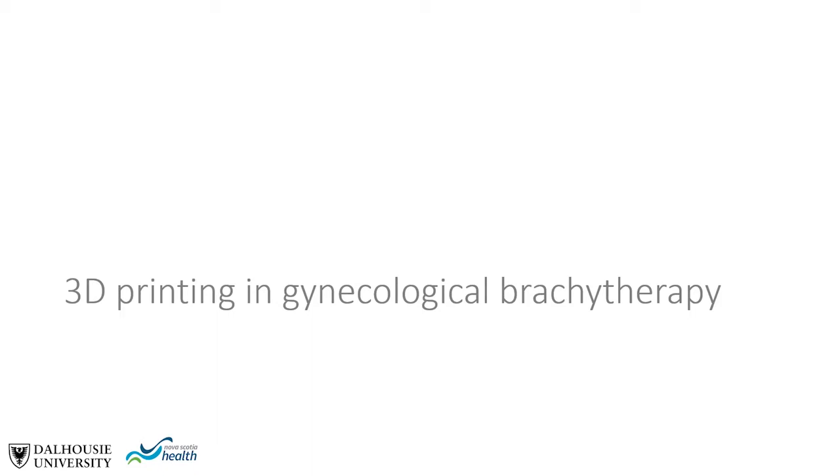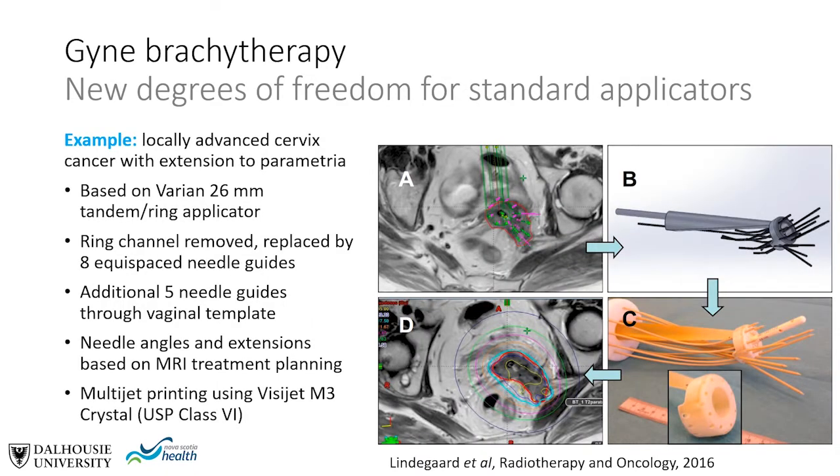Now we'll look at examples of 3D printing in gynecological brachytherapy. One approach is to extend the functionality of standard applicators. This example shows an applicator produced for treatment of locally advanced cervical cancer with extension to the parametria, based on a Varian 26 mm tandem/ring applicator where the ring channel was replaced by 8 equispaced needle guides. An additional 5 needle guides were included through the vaginal template, with needle angles based on MRI treatment planning, using multi-jet printing with VisiJet M3 Crystal, which is USP class 6 biocompatible.